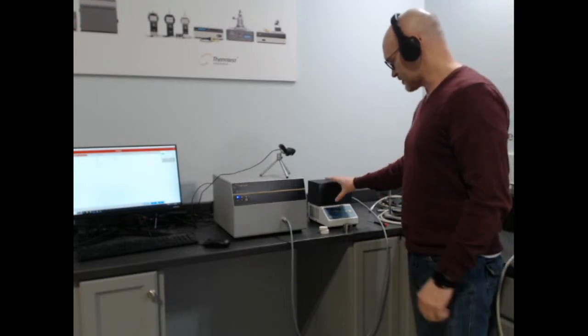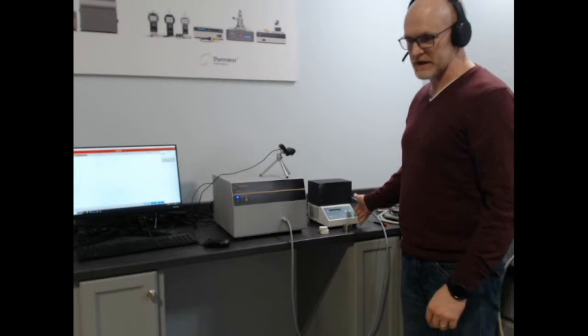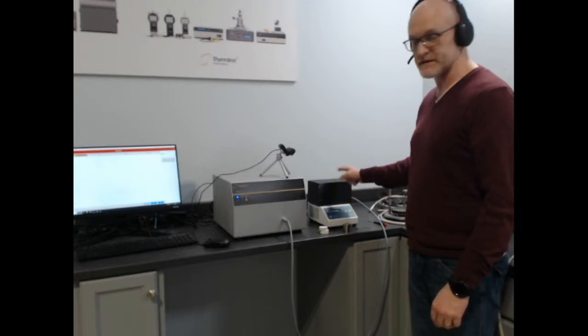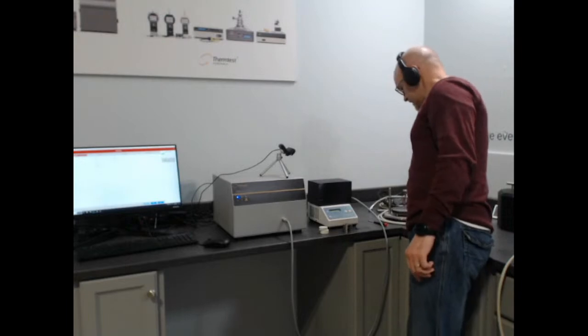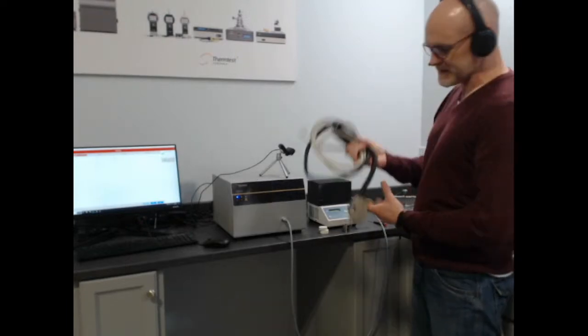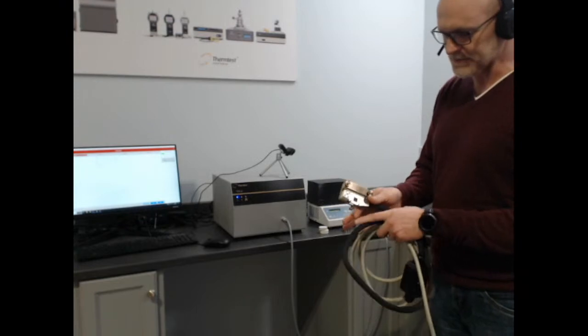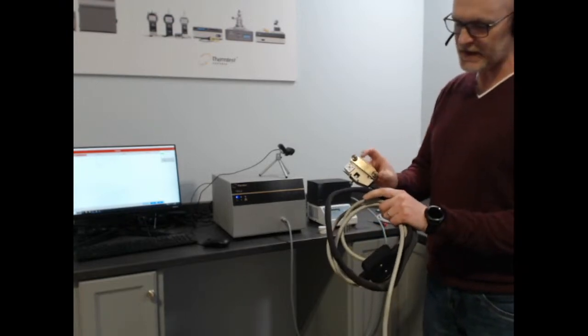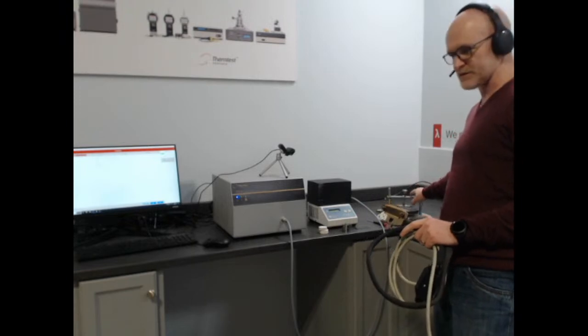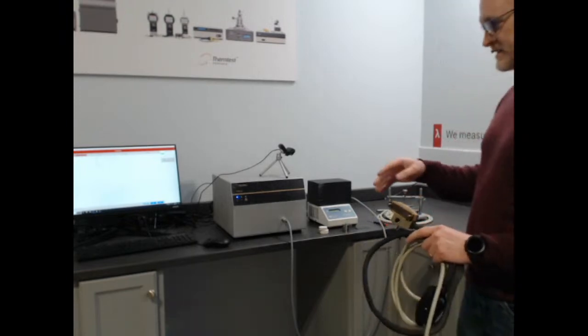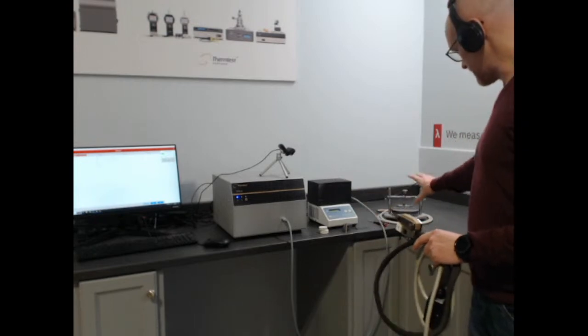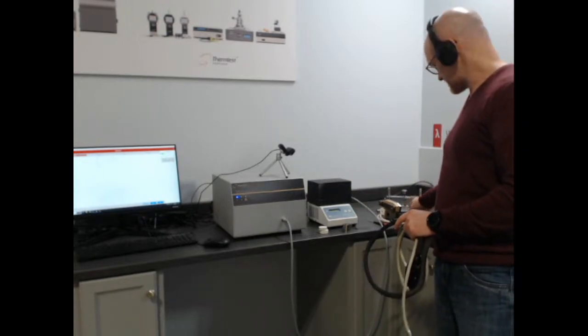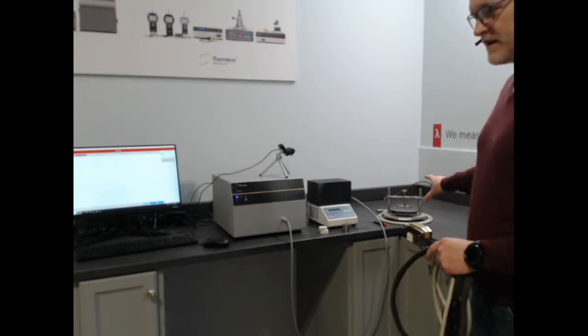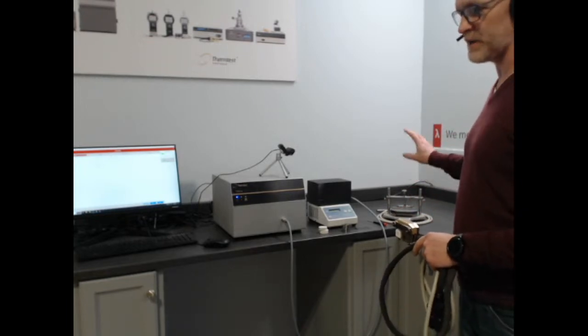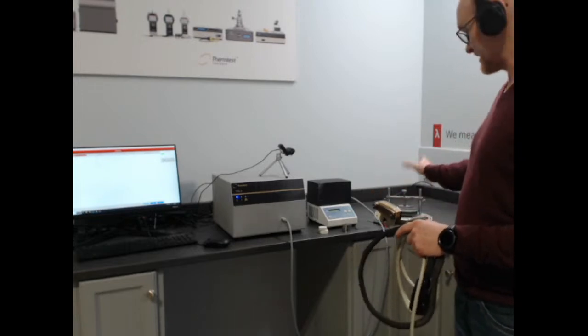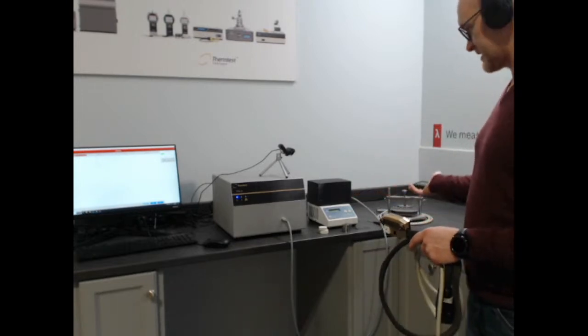So before I do show you our new thermoelectric dry bath, which goes from 0 to 100 C, we can talk about the other temperature options. This is the upgrade to the included adapter. So with the upgraded peak adapter on the room temperature sample holder that comes with the device, this unit can go from minus 75 to 300 Celsius. The sample holder that comes with the device allows for sample sizes of up to approximately 100 millimeters by 100 millimeters by 50 millimeters thick. So it does have advantages on sample size flexibility.